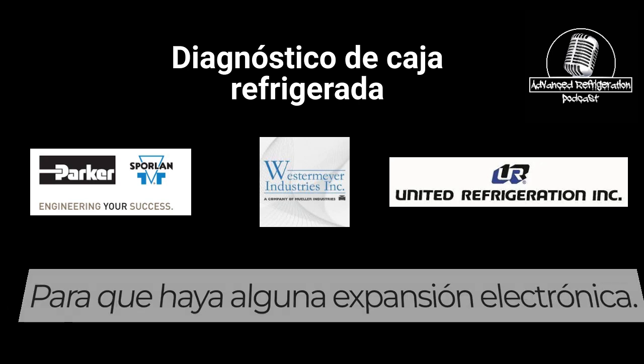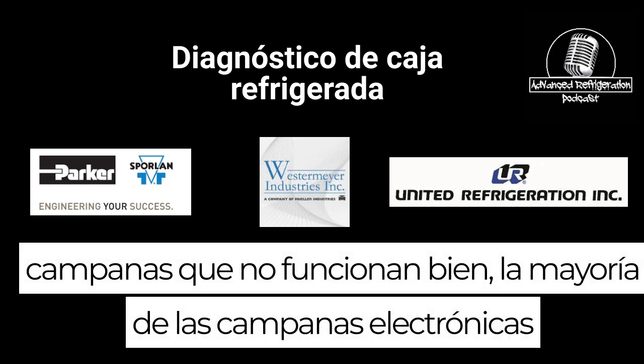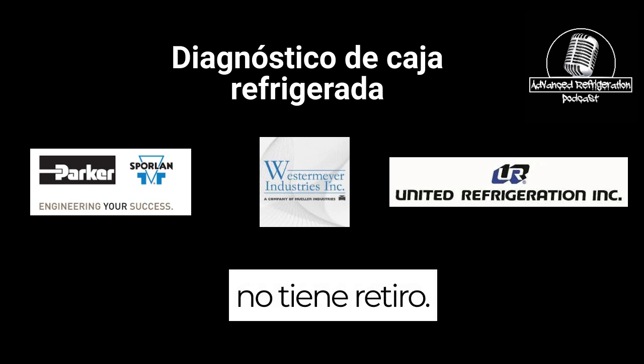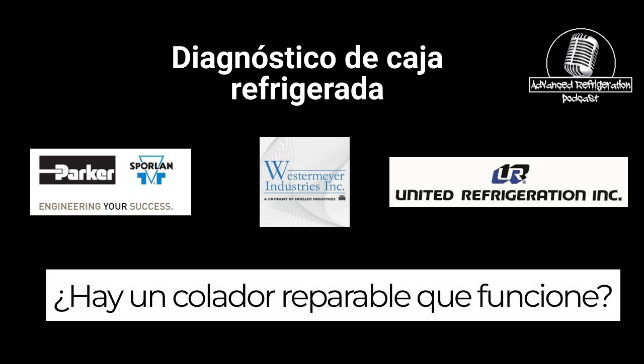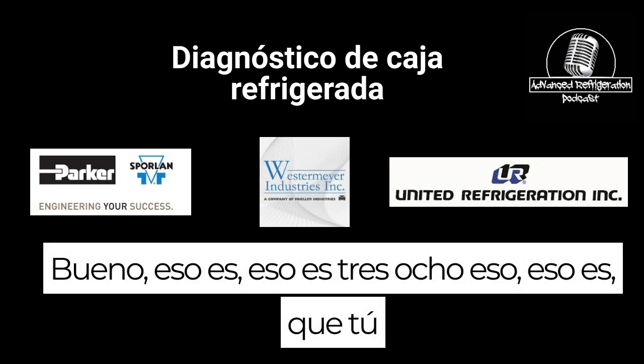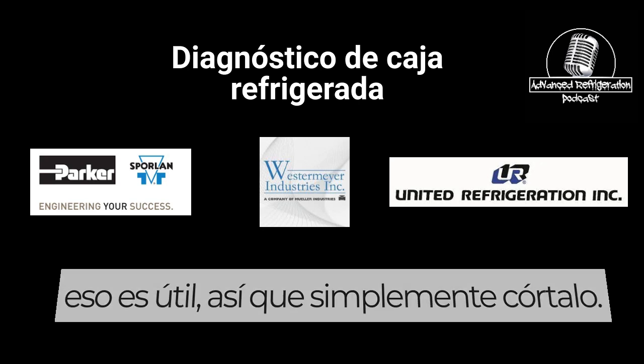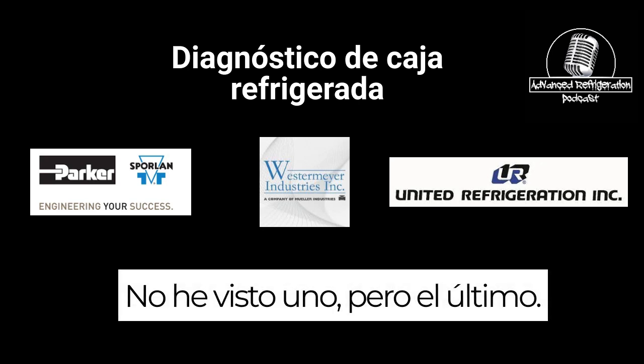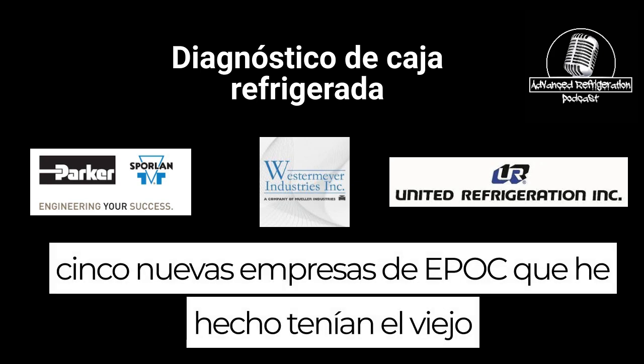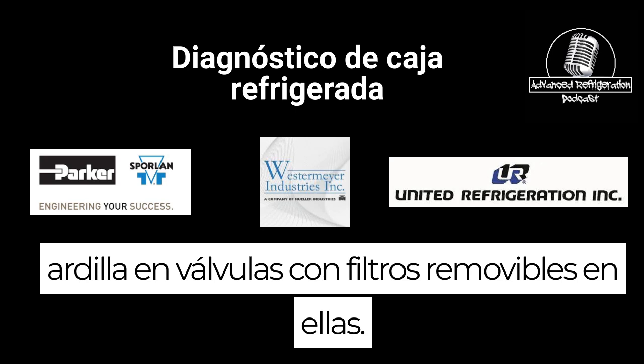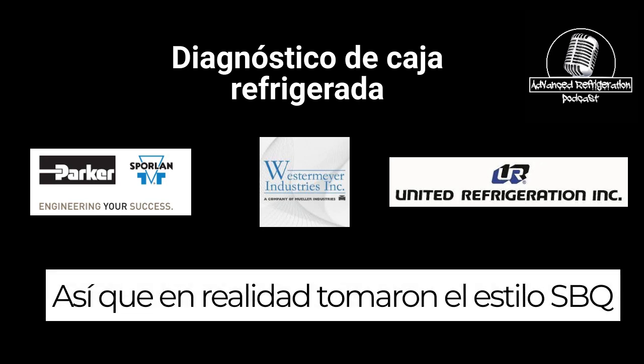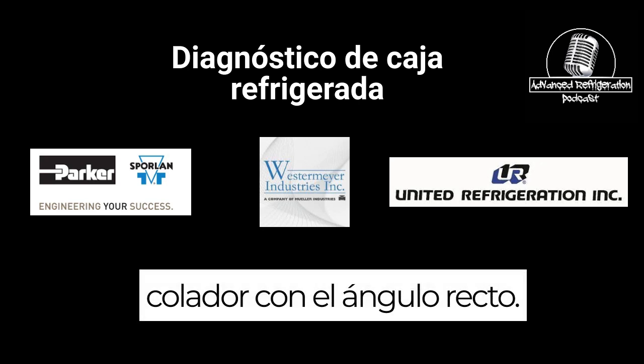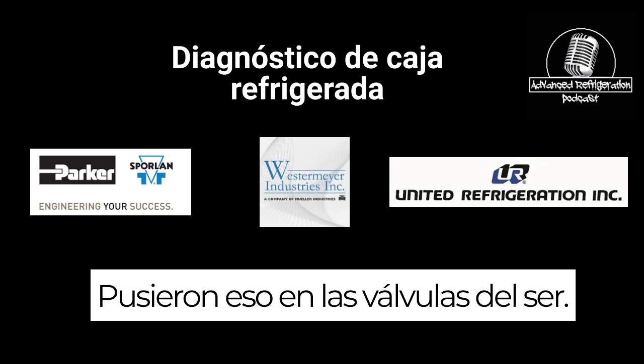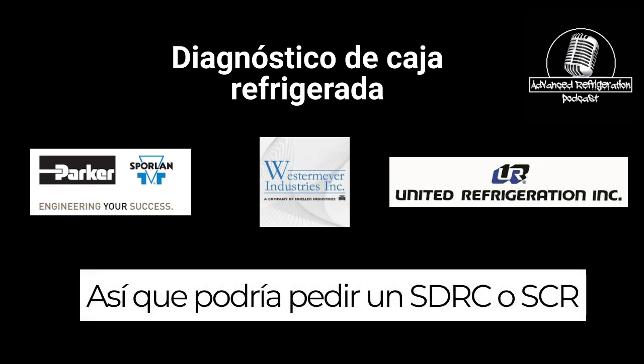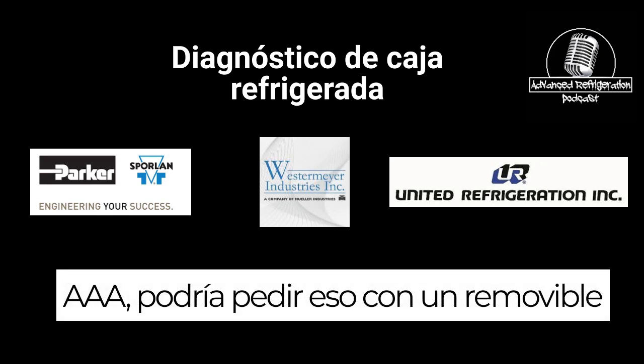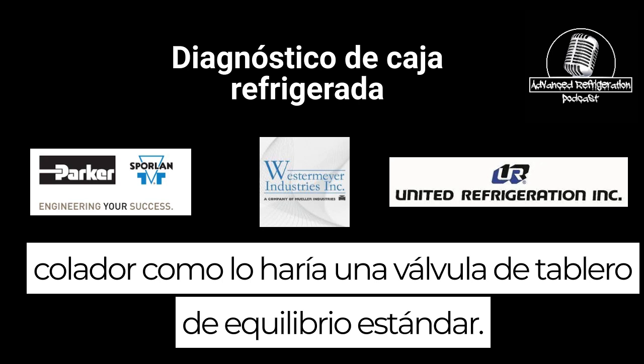See, yeah, that's one thing. Some electronic expansion valves don't. Well, okay, most electronic valves do not have a removable strainer. Is there a serviceable strainer that works well, 3/8, that you can install, so you don't have one that's serviceable and you can just cut it out? I have not seen one, but the last 5 startups I've done had the old Sporlan valves with removable strainers on them. They took an SBQE style strainer with the right angle and put that in the SER or SER valves now. So you could order an SERC or SER AA with a removable strainer, like a standard balance port valve would.